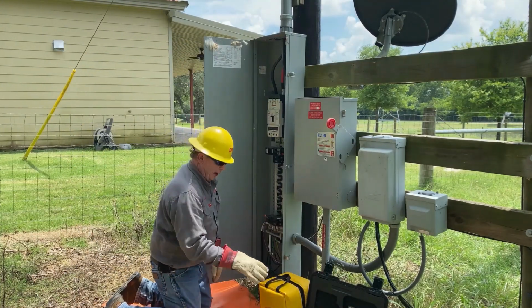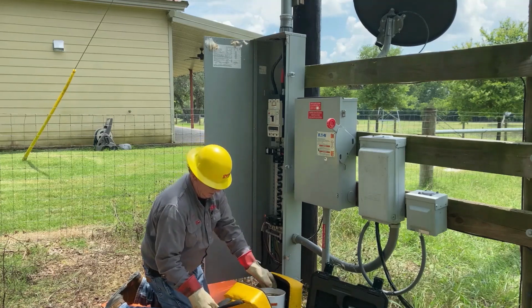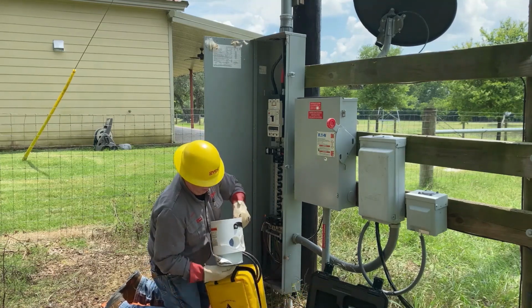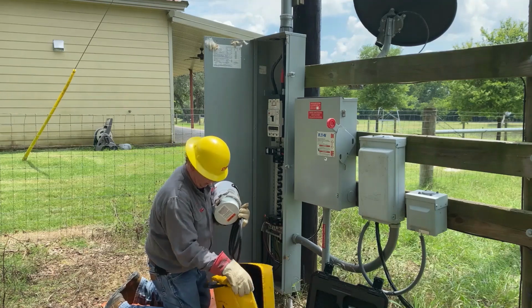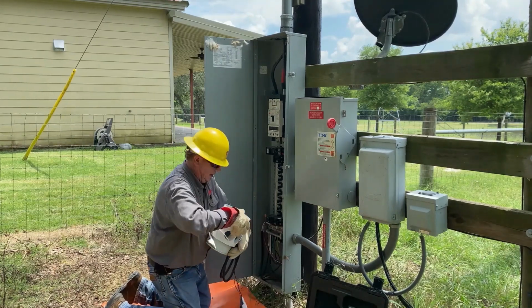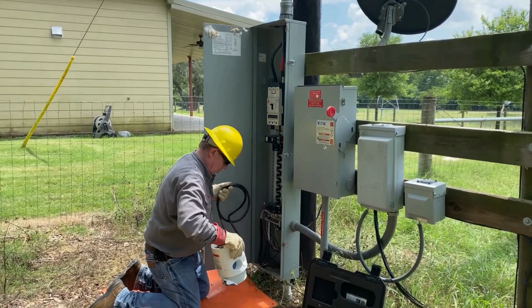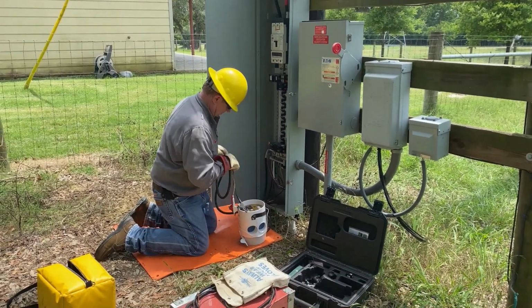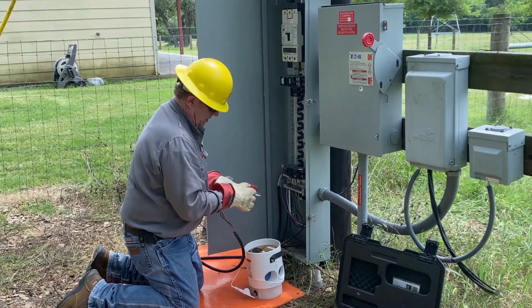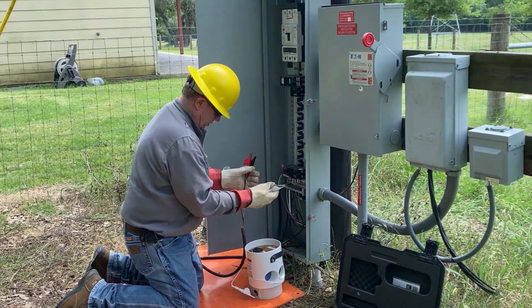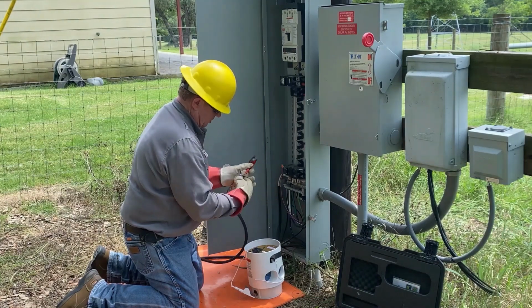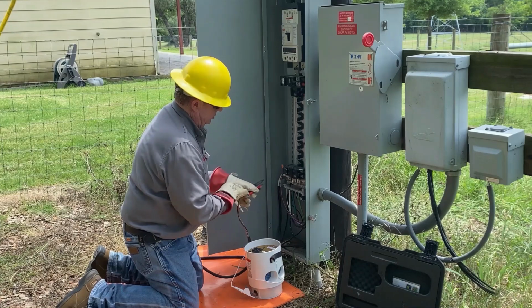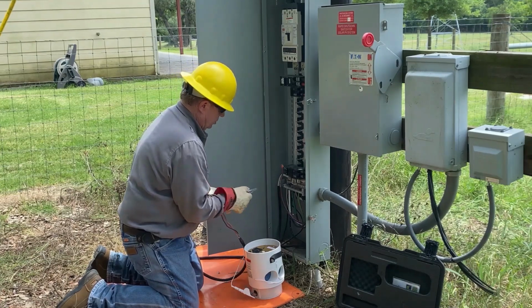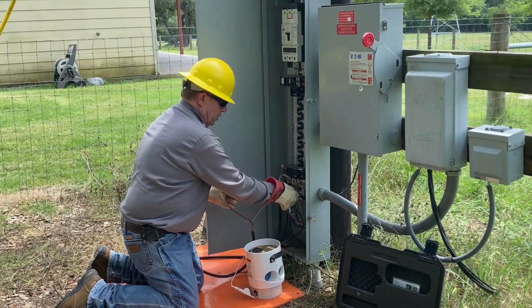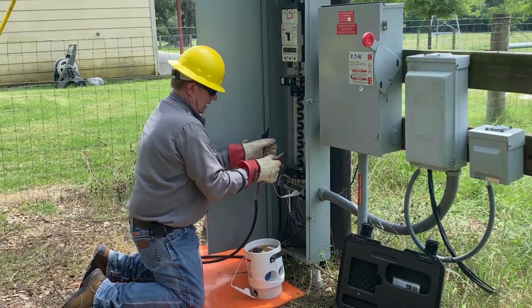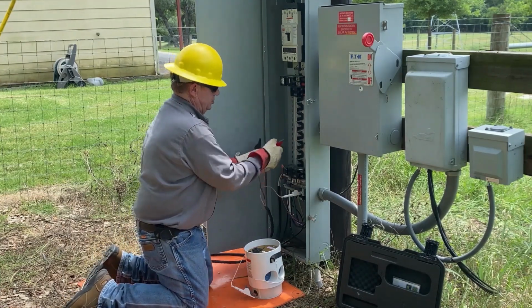So we're going to unpack the Super Beast. The Super Beast has the meter socket base on it, and we're going to connect it on one side. So white is going to go to the neutral bus bar so that it forces neutral currents back through all the bus and back to the neutral conductor. So we're going to clip it on right there. And then the hot leads, we'll bring them in and connect it straight to the bus.